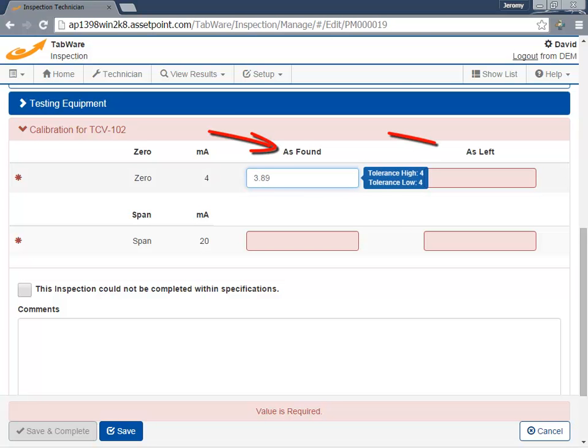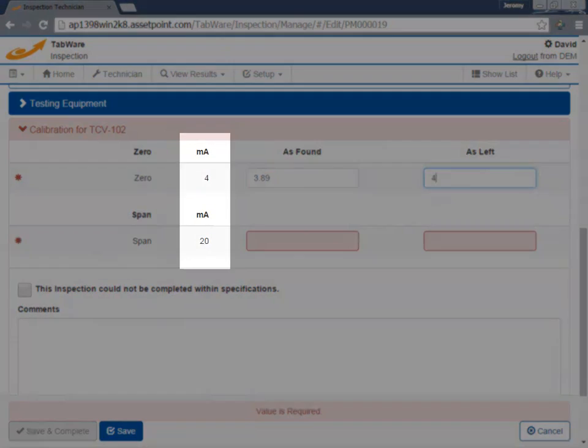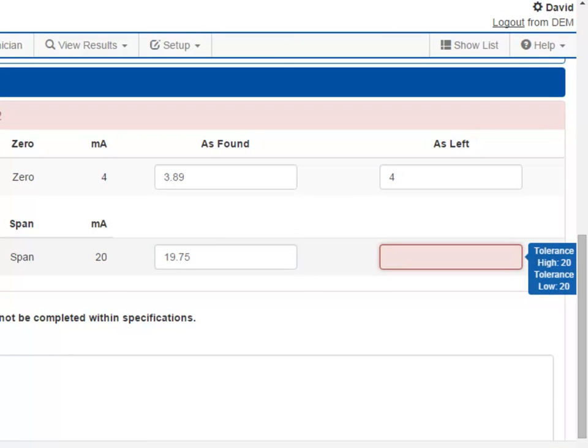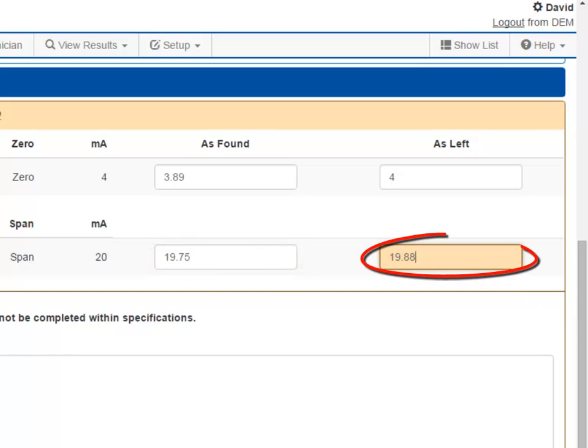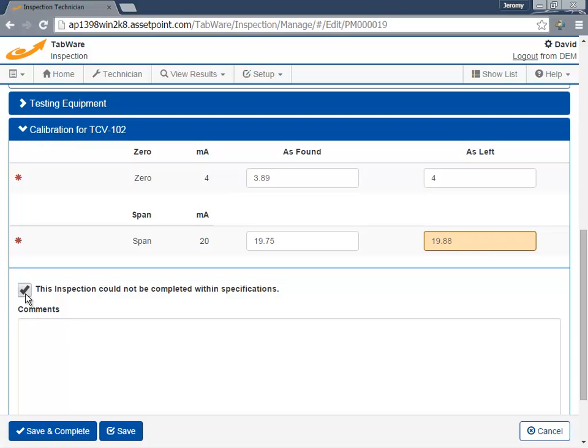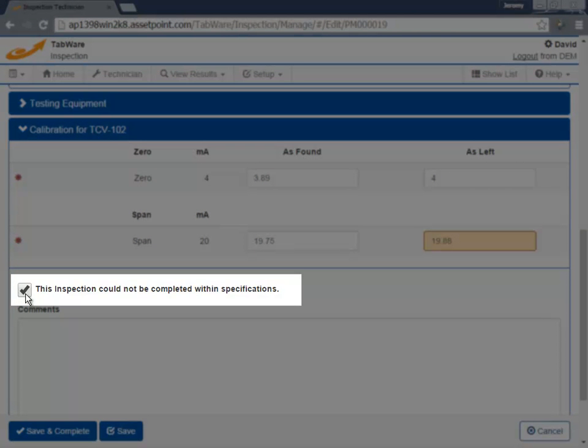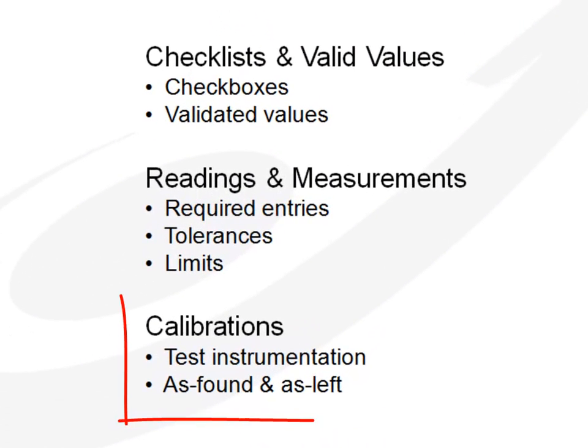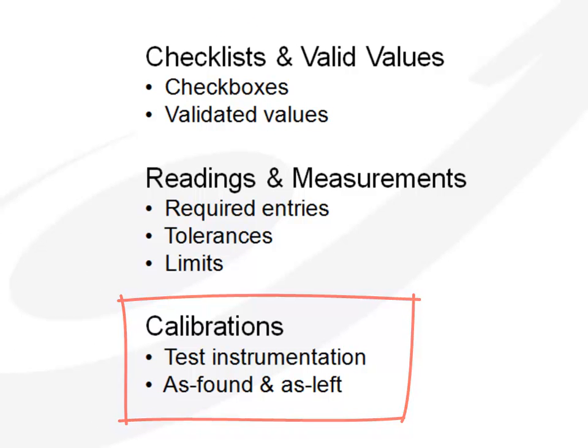Tabware also features as-found and as-left conditions, as well as desired values. Tabware allows the user to define a failure based on the entered value, so while a bad reading as an as-found condition may be acceptable, as an as-left condition, the same reading indicates a failure. For this scenario, we have failed an inspection. We may save the inspection for now and try to restore the equipment to a passable state, or we must indicate that this inspection could not be completed within specifications. Special work order routing and email notifications can notify the maintenance supervisor or manager of a failed inspection. Scenario 3 called for test instrumentation and standards, required entries with upper and lower tolerances, and documenting as-found and as-left conditions.